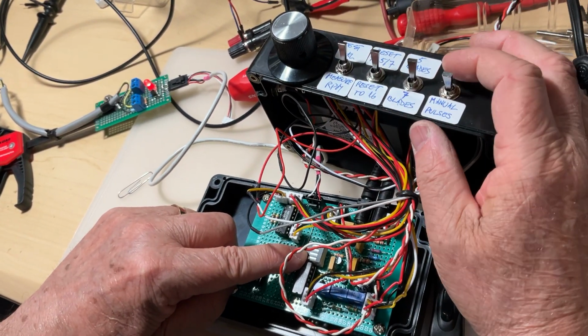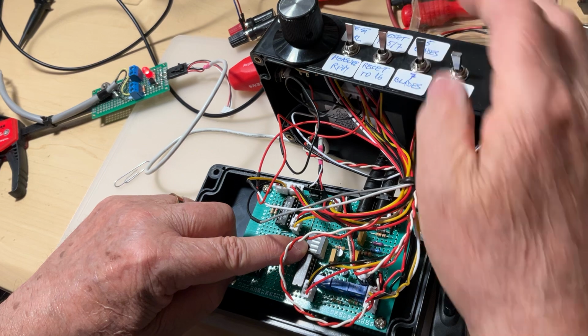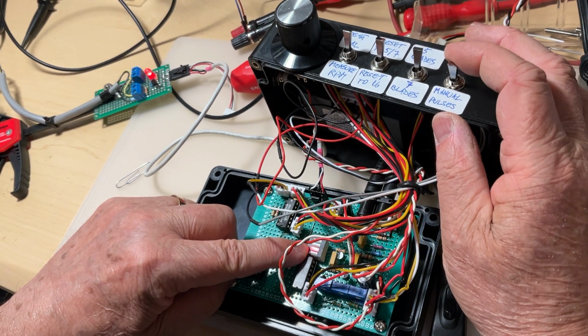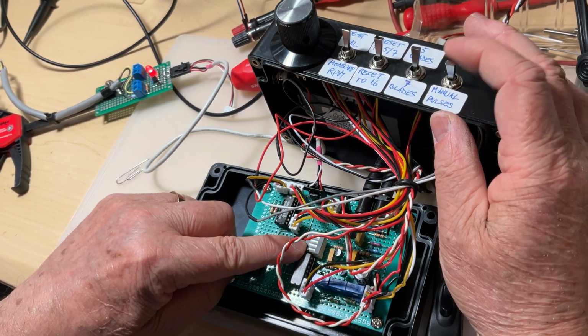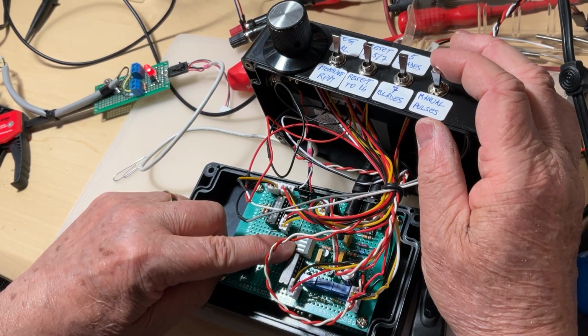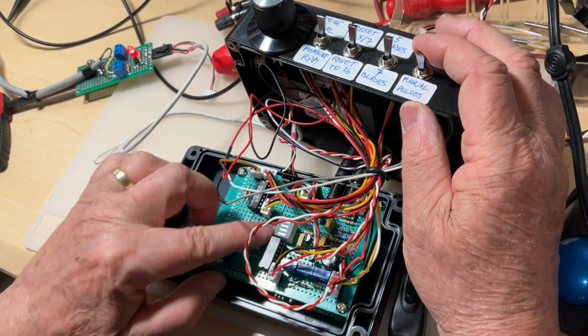So if I put it on test, now we're not measuring the RPM, we're testing it. 1, 2, 3, 4 - at the 5th pulse, it goes back to 0. So this is for 5 blades. Again, 1, 2, 3, 4, 5. Now we put it on 7 blades.